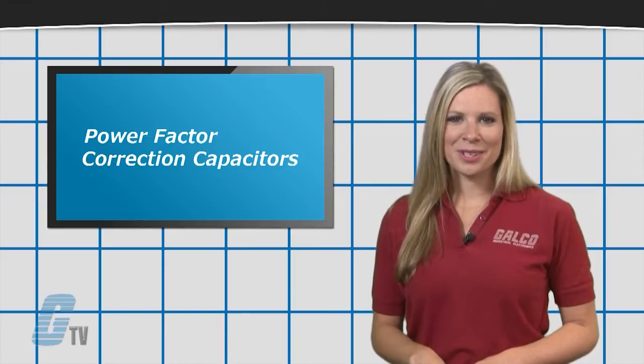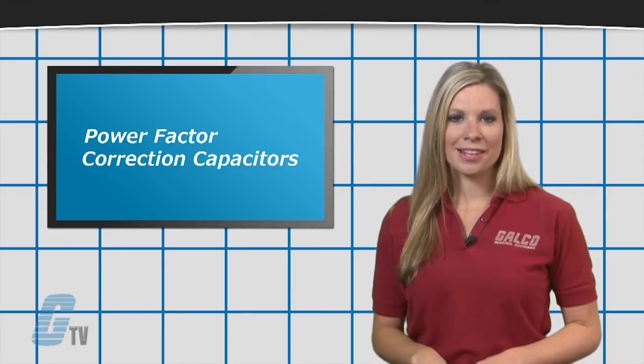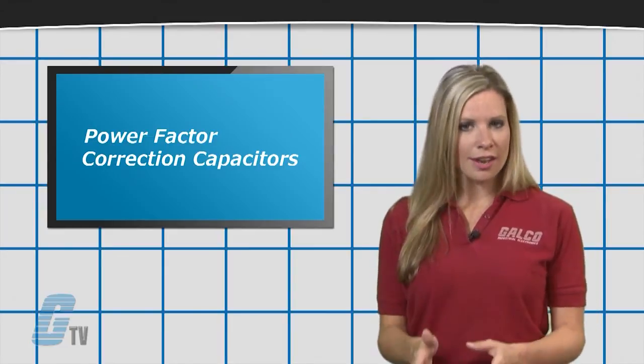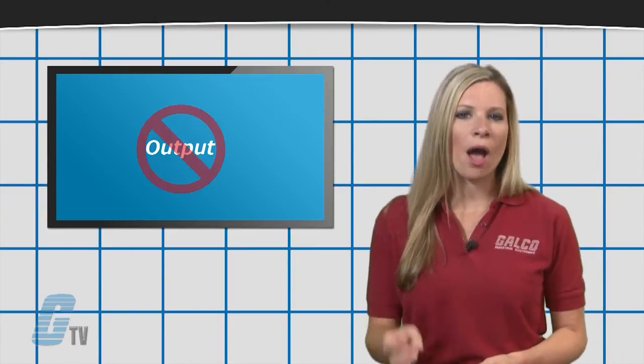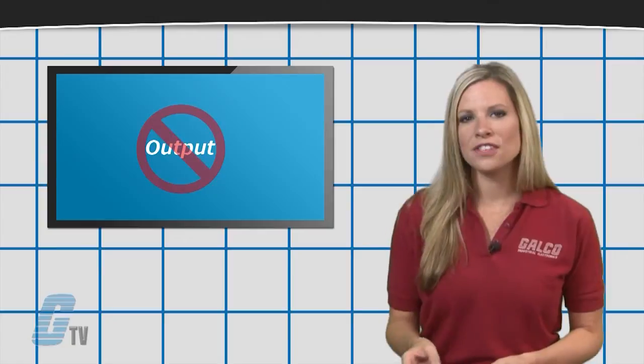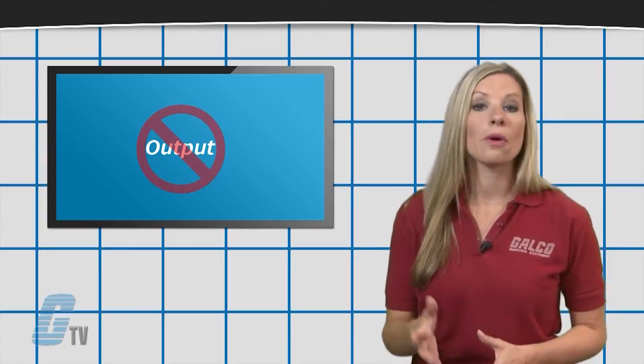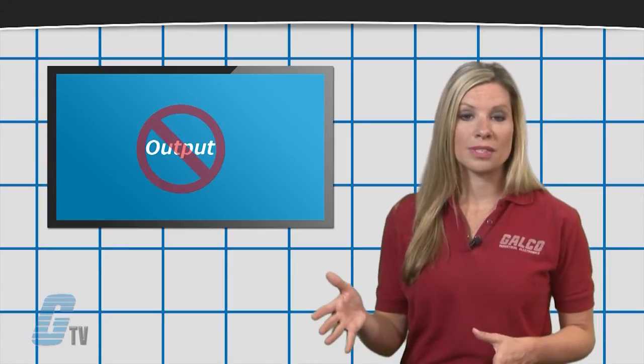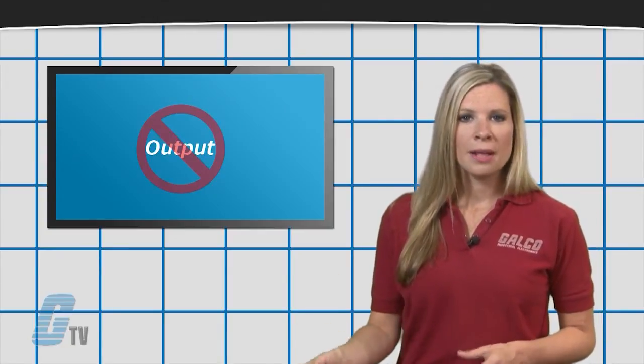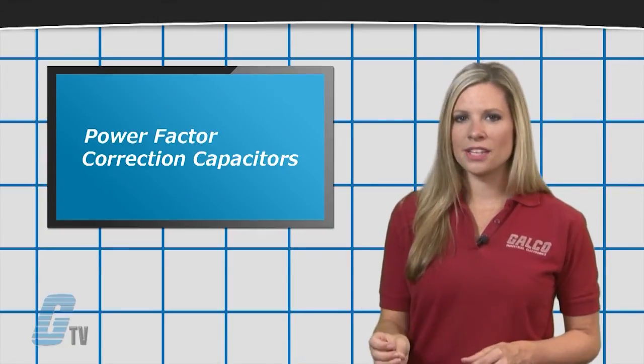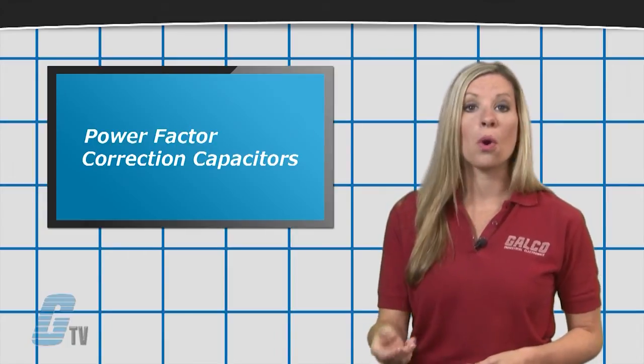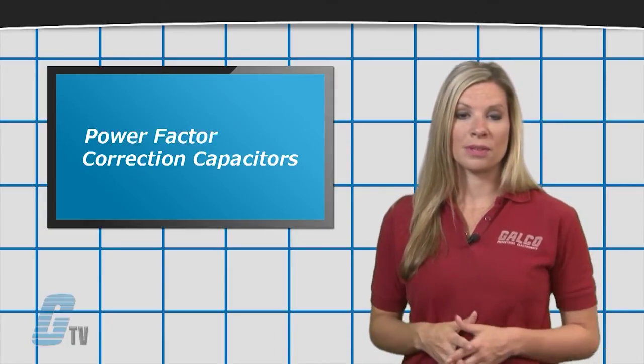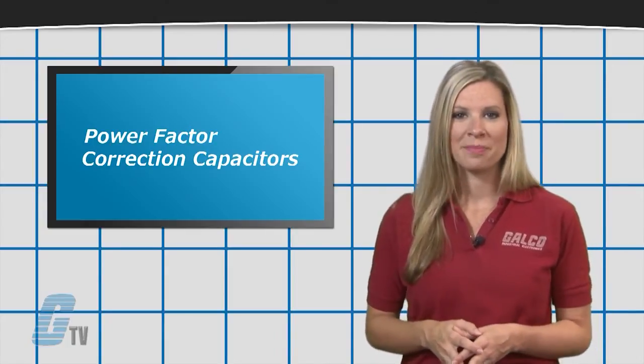Power Factor Correction Capacitors should never be installed on the output of a soft starter or variable frequency drive, but should be installed in the front of the soft starter or variable frequency drive.